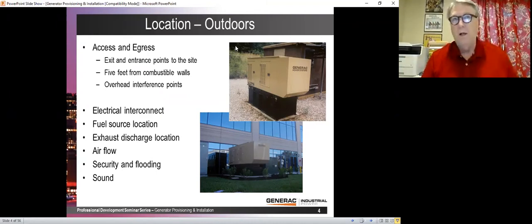Now you might say, well, I've got a standby generator by my house. It's not 5 feet. Well, no, that's another little exception. If the generator is in an outdoor non-combustible enclosure, and it's shown that that will prevent a fire from causing something next to it to catch on fire, then you can put it within 18 inches. And so with these residential generators, typically they're all serviced from the top. So you don't need the 3 foot 6 inch clearance for your electrical, and you can put those as close as 18 inches.